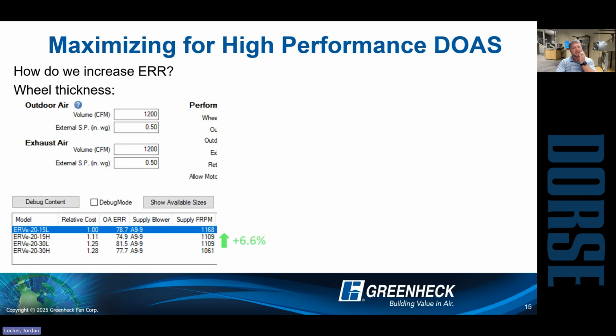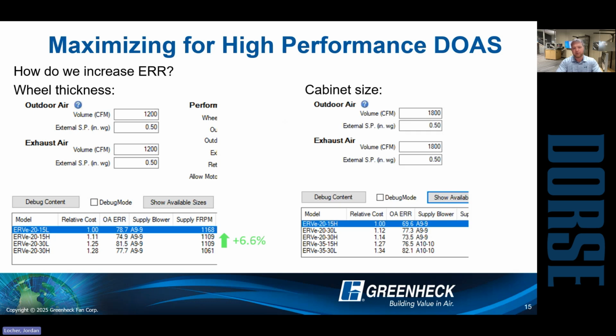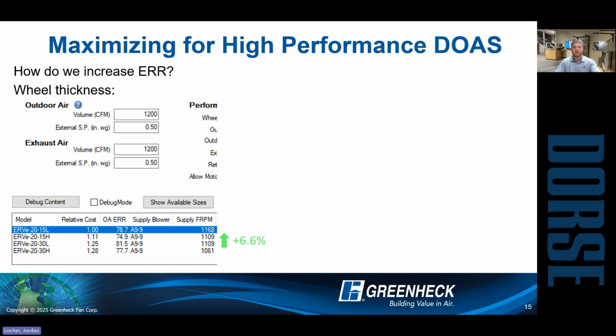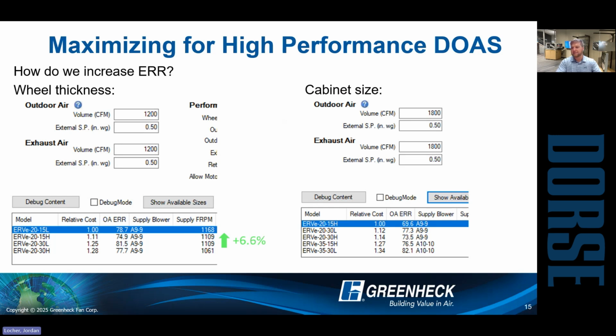To show you an example of that, if I increase my wheel thickness, look at the top left. If I do an ERVE 20 with a 1.5 inch wheel, I'm probably sitting around 78% ERR. However, if I go to the ERVE 20-30L, which uses a 3-inch thick wheel, I can jump up to 81.5% ERR. So that's approximately a 6.5% bump in energy recovery just by going with a thicker wheel. The other one is cabinet sizing.